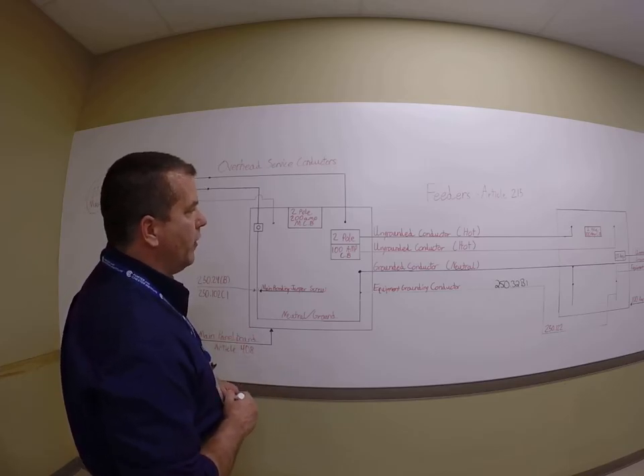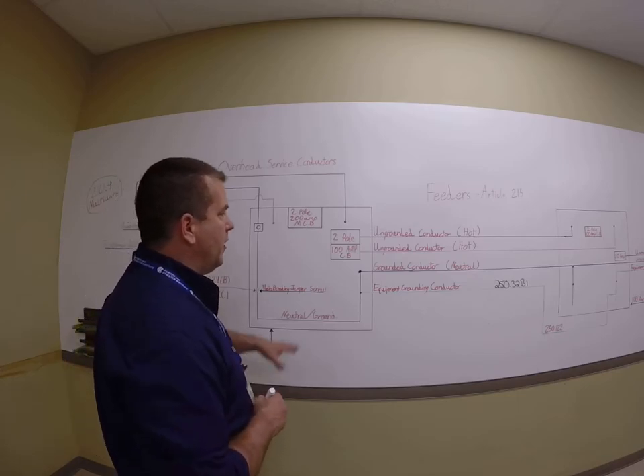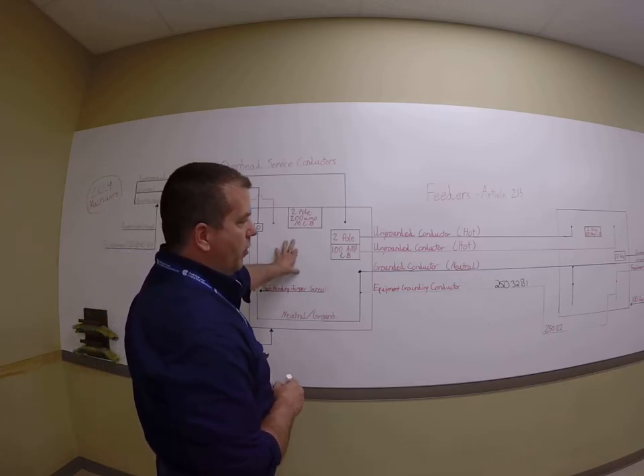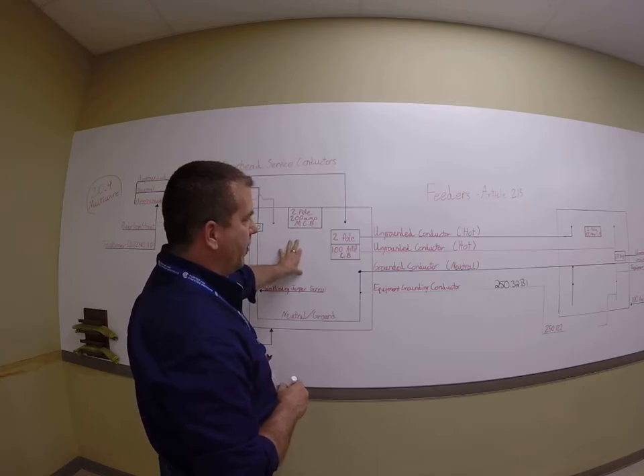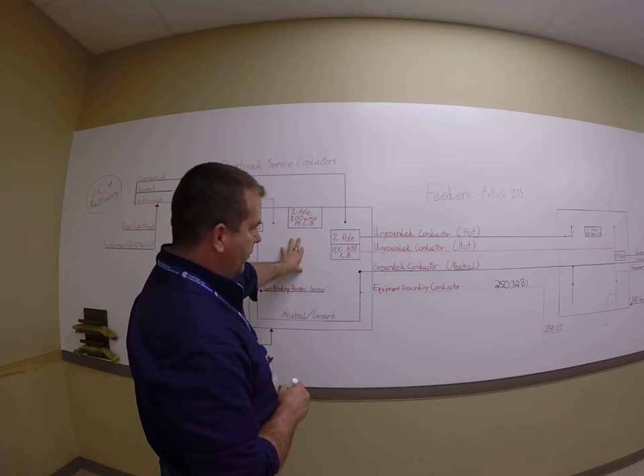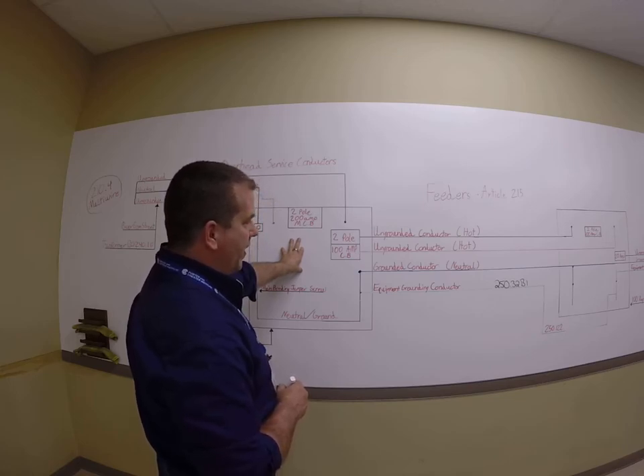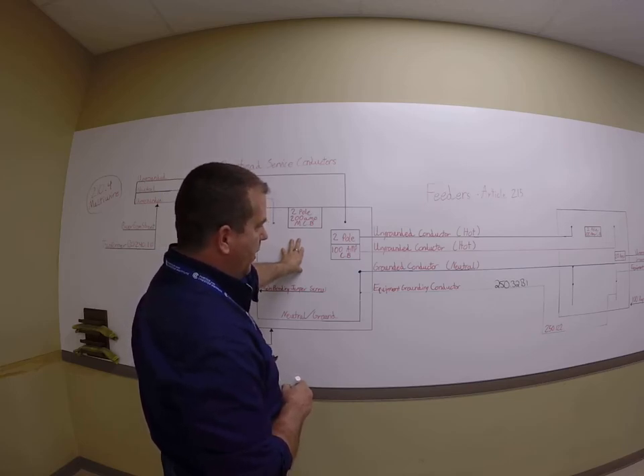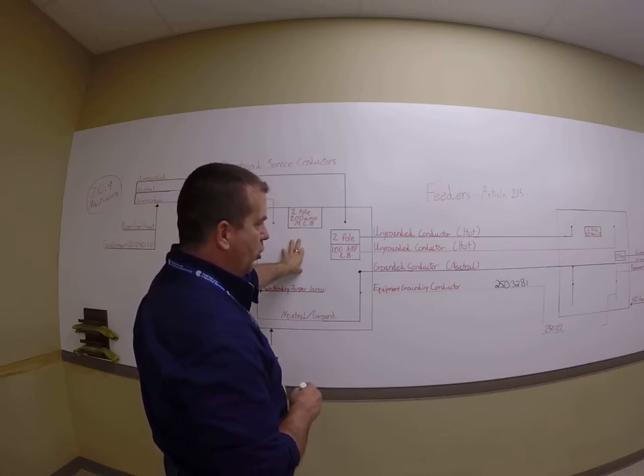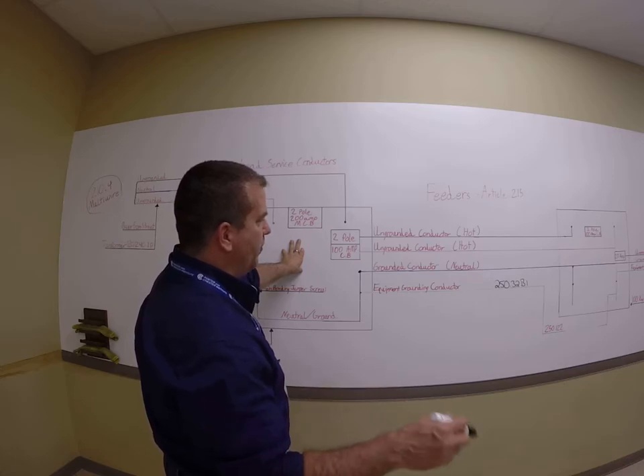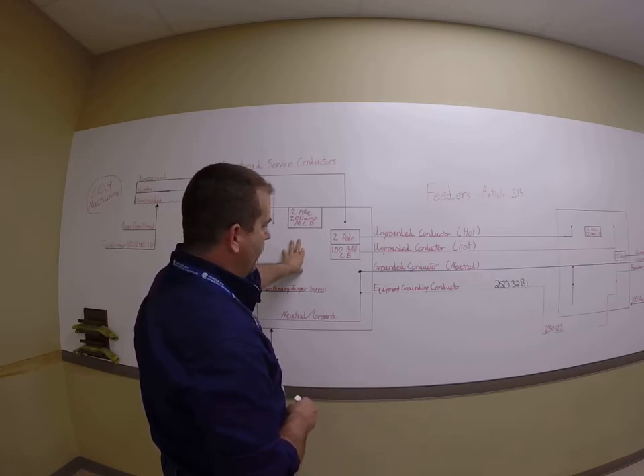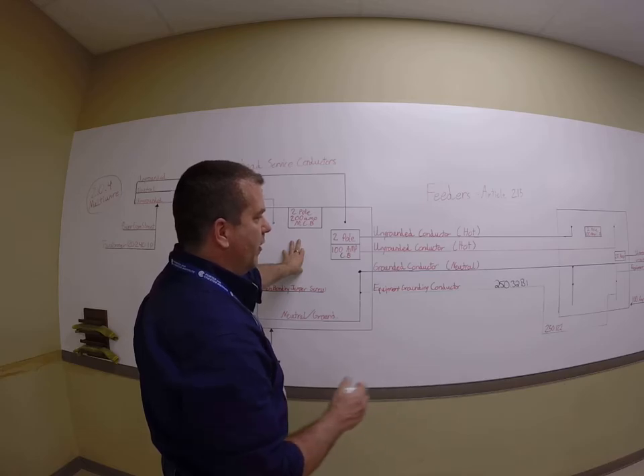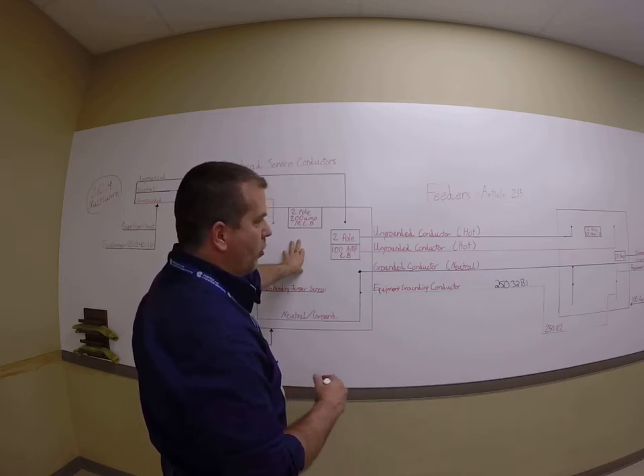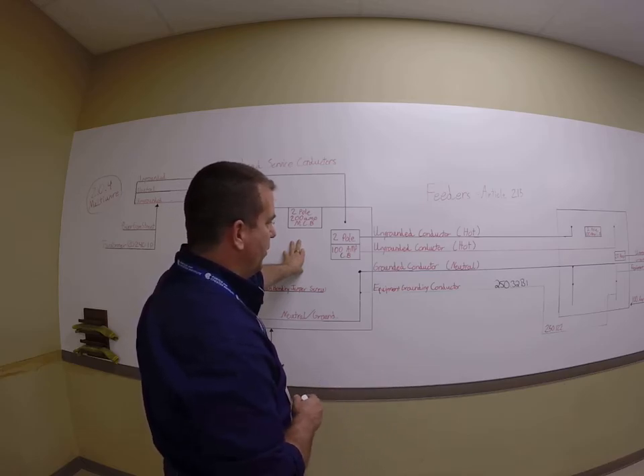Now there's a reason why we do this. The first primary reason is this is the service, and you're only putting in your main bonding jumper at the first form of disconnect of your service when you enter the building. And oftentimes, required by code, the main service disconnect, if it's in the building, has to be as close as practical to entry of the building. And I've been with inspectors that want it immediately on the other side of the wall, or no more than 10 feet from entry into the building.